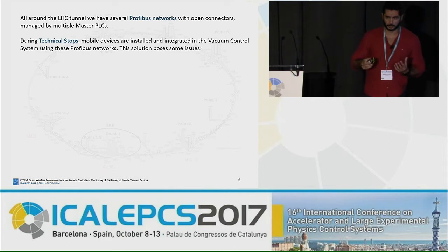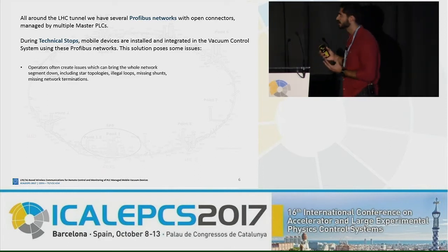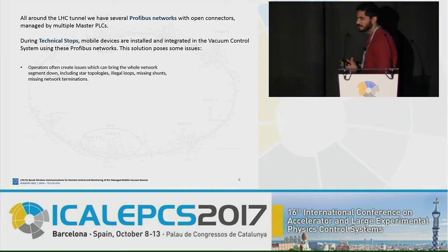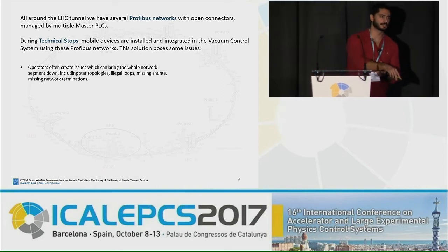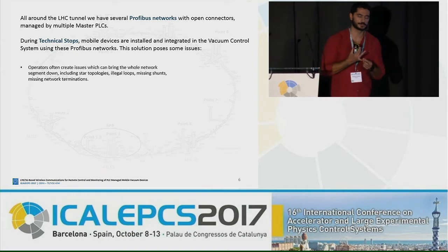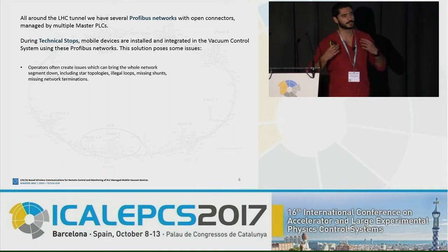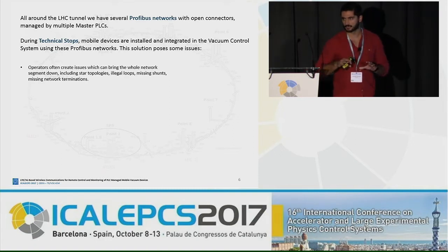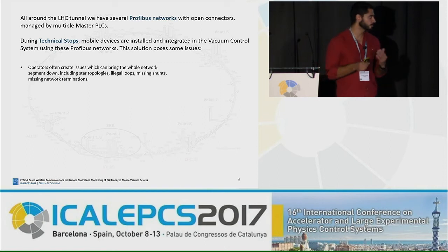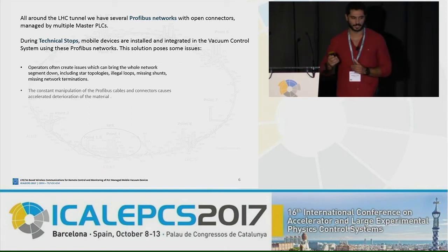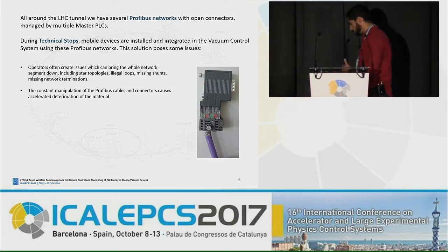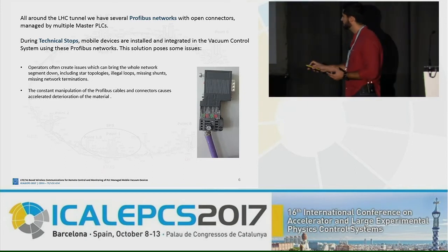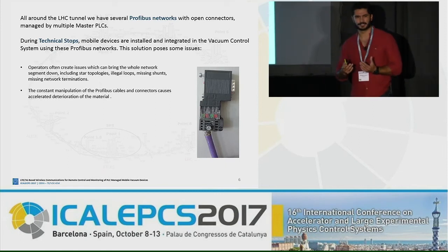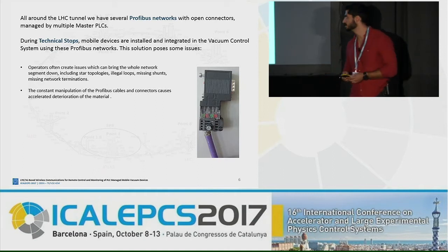But due to the way that we do this with wired Profibus networks, there are some issues that sometimes hamper operation. The first one is that the people actually in the tunnel installing these devices are not control experts and are not field bus experts. So quite often they create a wrong topology, they forget a shunt, they forget a termination resistance. And if you do this, you often bring the whole network down, so you affect not only your device, but all the devices in this network. Secondly, the constant manipulation of cables and connectors, as you see here, degrades the material early. This is not supposed to be connected and disconnected hundreds of times in one year.